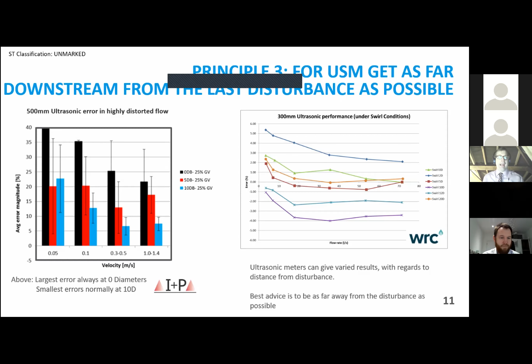Something that will help out ultrasonic meters is putting on more paths, more transducers. The more transducers you have, the more paths you can have, and you get a better sample, a better representation of what's happening in the main, and you get more accurate and more precise metering and results. The other thing that's really important for ultrasonic metering is to take into account the wall thickness and also the temperature of the water. The temperature of the water affects how quickly sound travels through water.